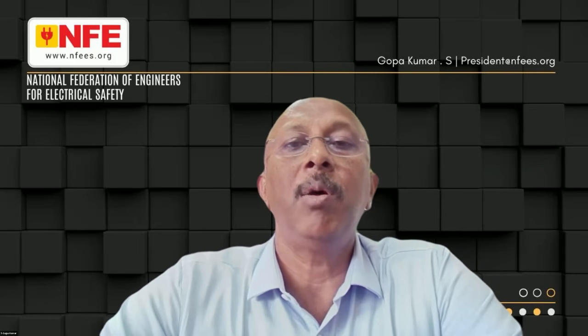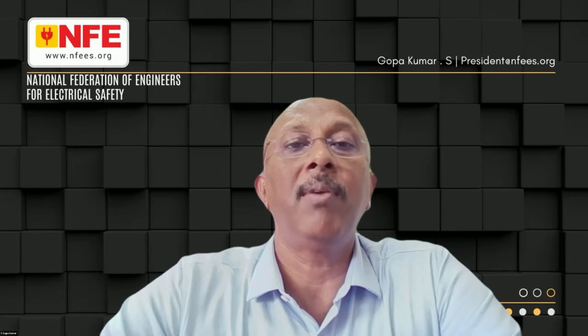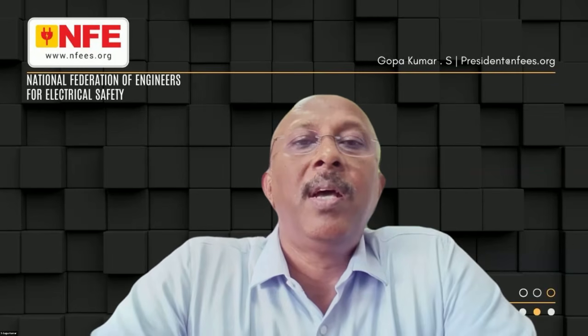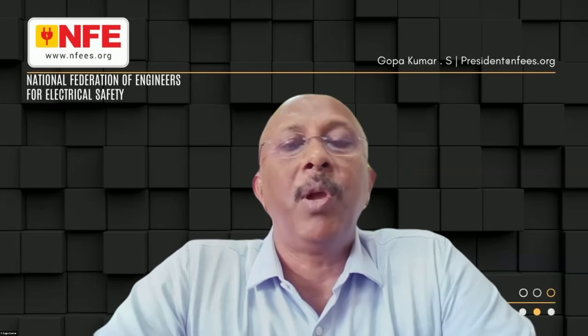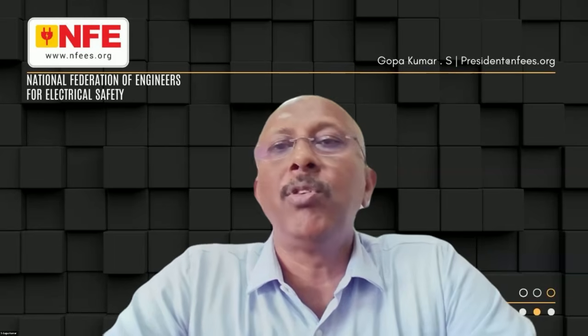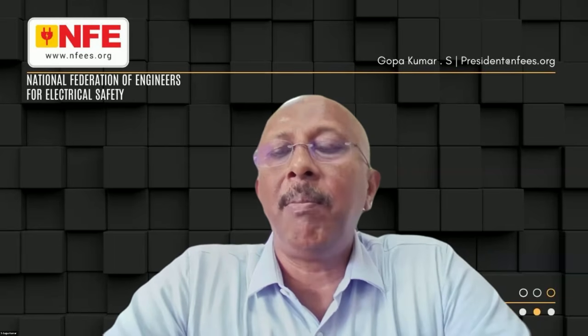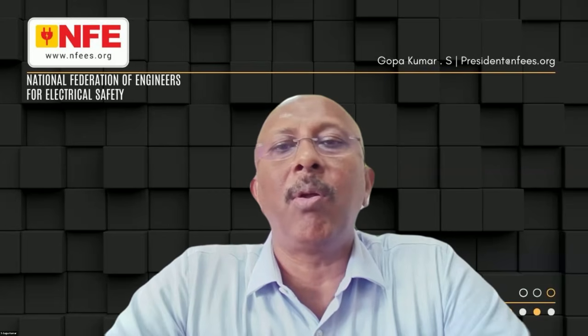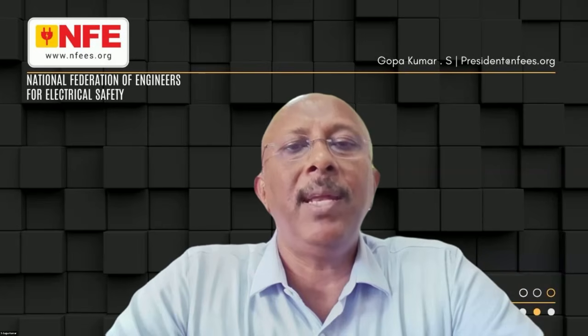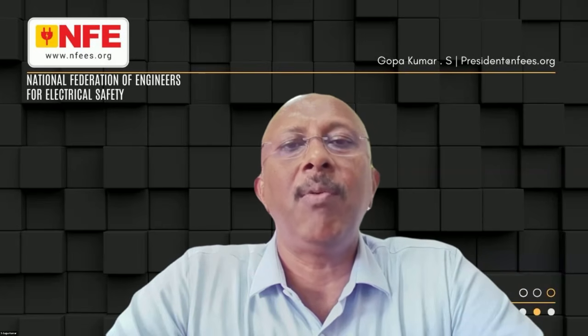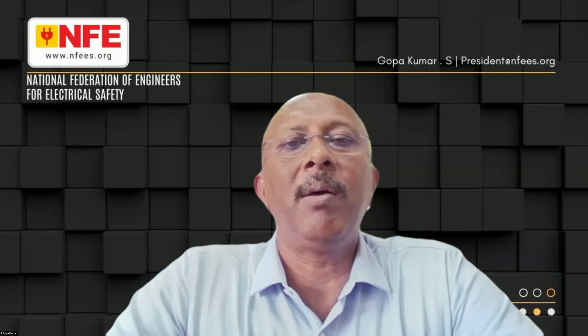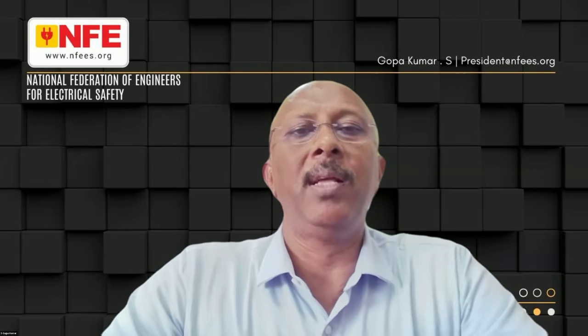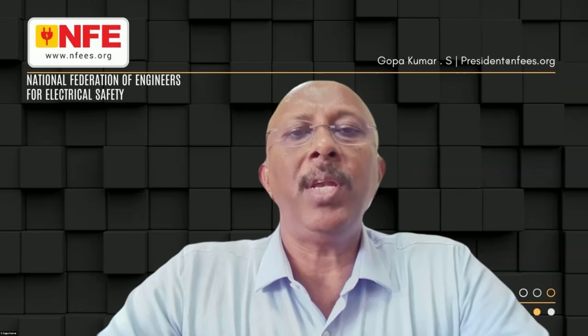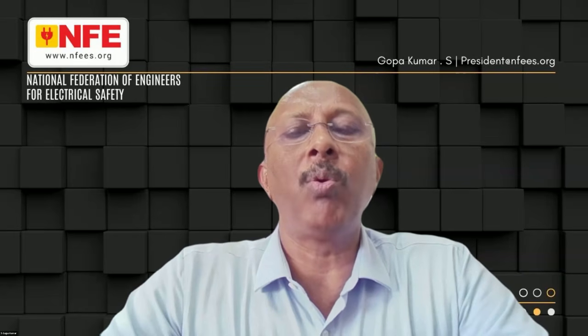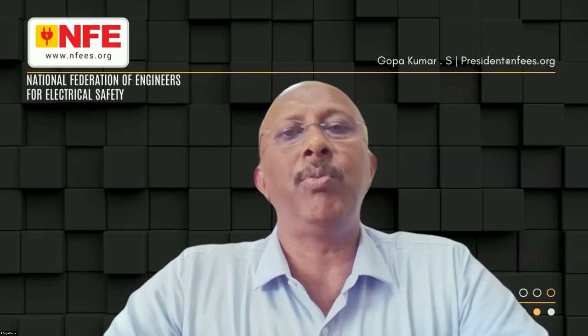Why does a cautery machine in the operation theater create a burning effect on the patient, even when earthing values are okay? Actually, this is a very serious question. A cautery machine is used for removing some parts or cutting the skin. If the temperature or the frequency of this device is different from what is required, instead of cutting, it will create a big hole on the skin. Instead of making a small cut, the cut becomes much bigger. Probably out of 1,000 operations, maybe 1 or 2 accidents are also happening, which is supposed to be 0.